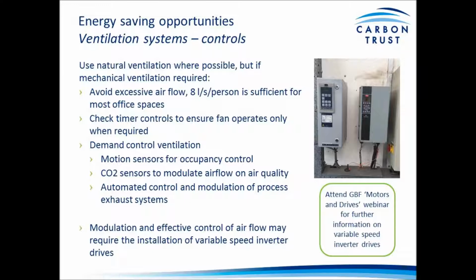Varying fan speed. You need a variable speed drive to vary the speed that the fan motor is operating at. It needs to be paired with suitable controls, but it can be very effective, as due to fan motor laws, if you reduce the fan speed by around 20%, it results in an energy saving of around 50% of the motor, which is obviously substantial for a not huge reduction in your airflow. So it's very worth considering, and if you want more details on motors and drives, I'd encourage you to watch our GBF webinar on motors and drives, which will give you more details about implementing variable speed drives on motors and fans, and how that can result in substantial energy savings.